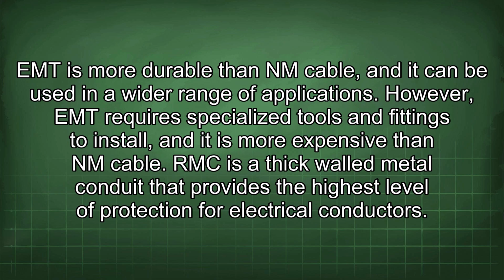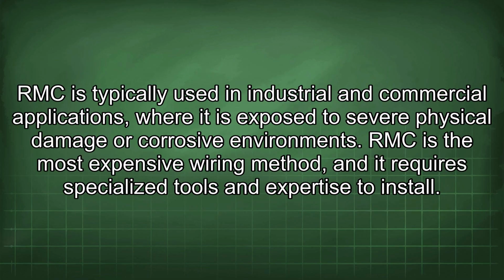However, NM cable is not suitable for use in wet or damp locations, or in locations where it is exposed to physical damage. EMT is a thin-walled metal conduit that is used to protect electrical conductors. EMT is more durable than NM cable, and it can be used in a wider range of applications. However, EMT requires specialized tools and fittings to install, and it is more expensive than NM cable. RMC is a thick-walled metal conduit that provides the highest level of protection for electrical conductors. RMC is typically used in industrial and commercial applications where it is exposed to severe physical damage or corrosive environments. RMC is the most expensive wiring method, and it requires specialized tools and expertise to install.